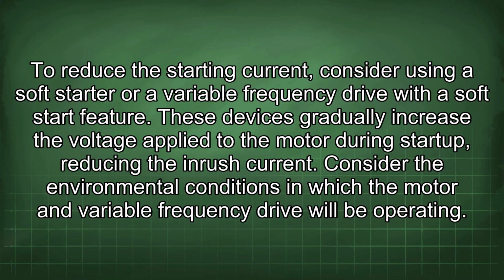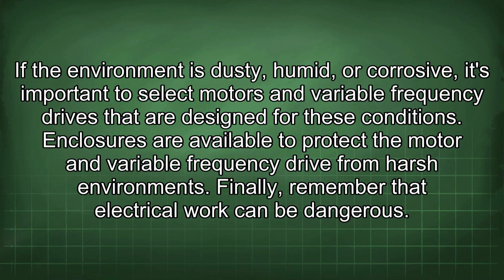Consider the environmental conditions in which the motor and variable frequency drive will be operating. If the environment is dusty, humid, or corrosive, it's important to select motors and variable frequency drives that are designed for these conditions. Enclosures are available to protect the motor and variable frequency drive from harsh environments.